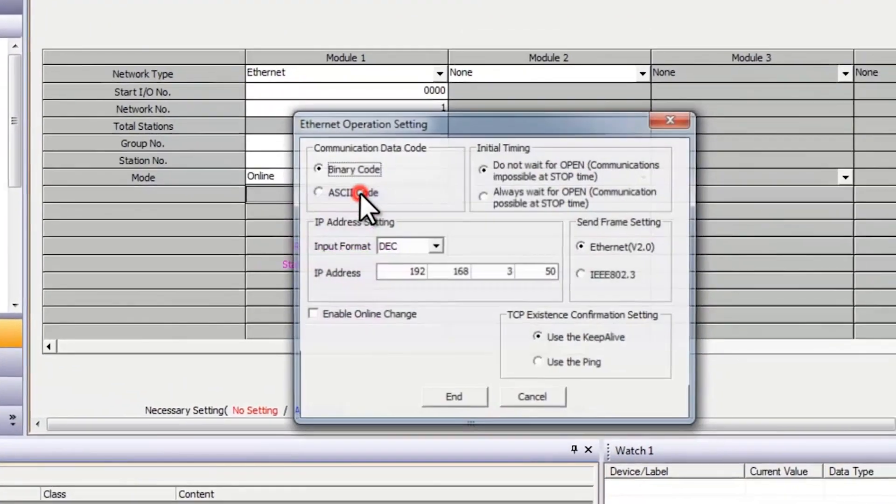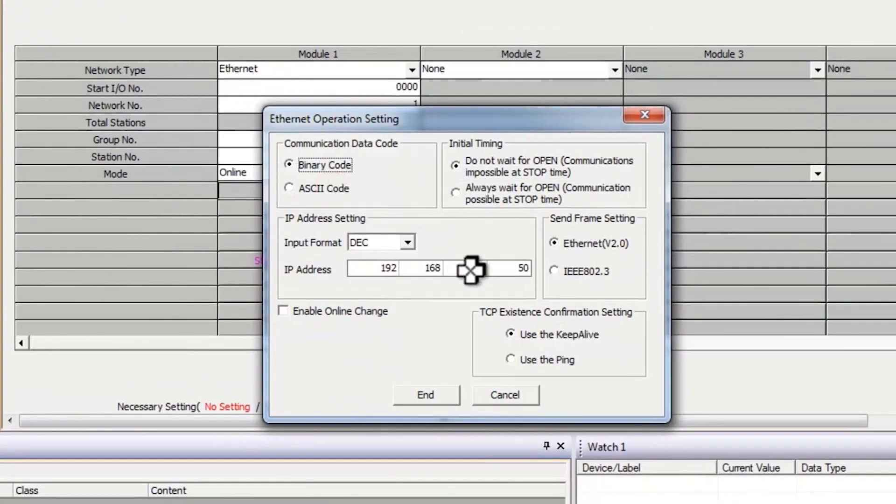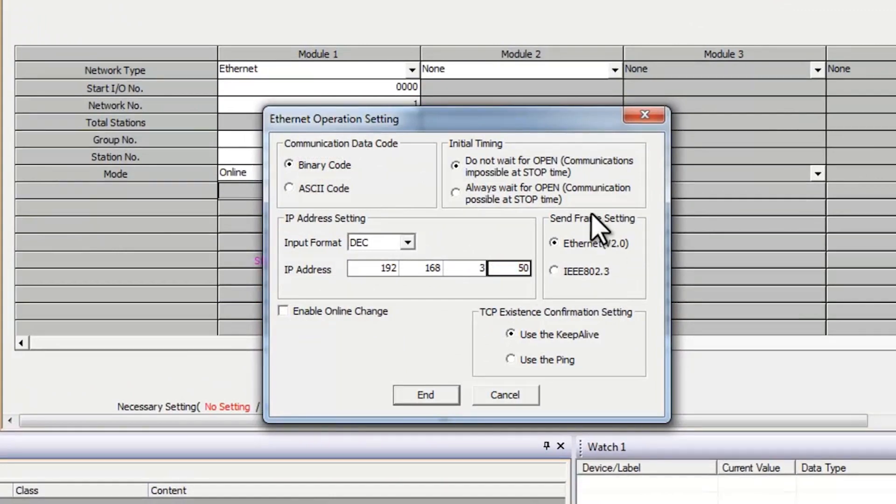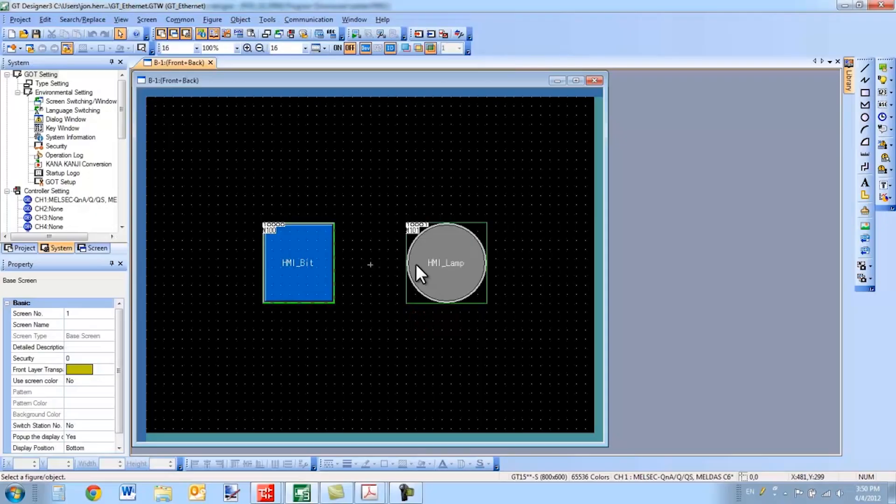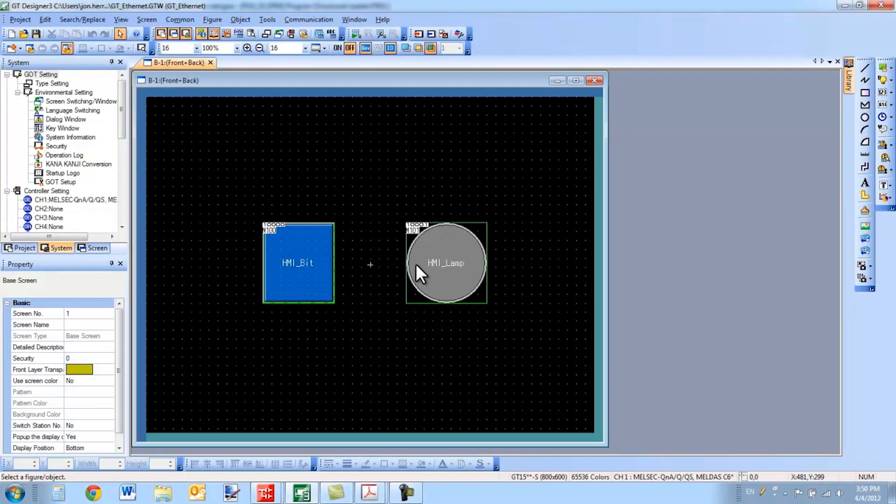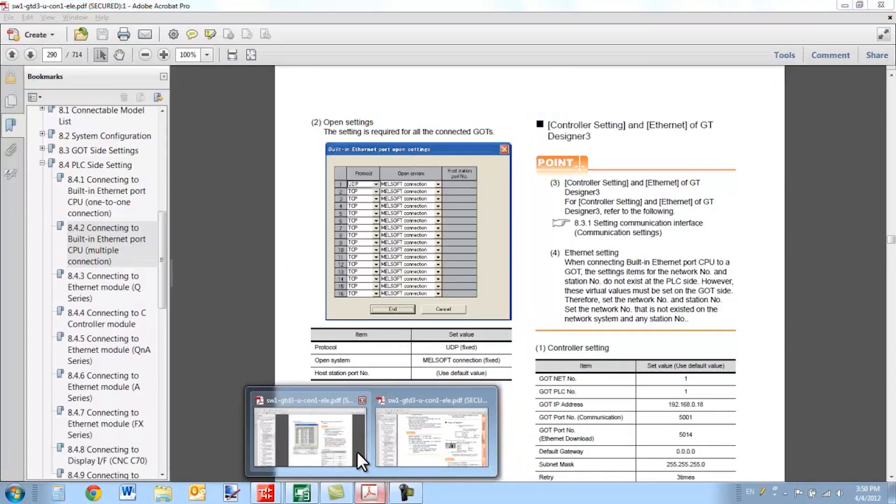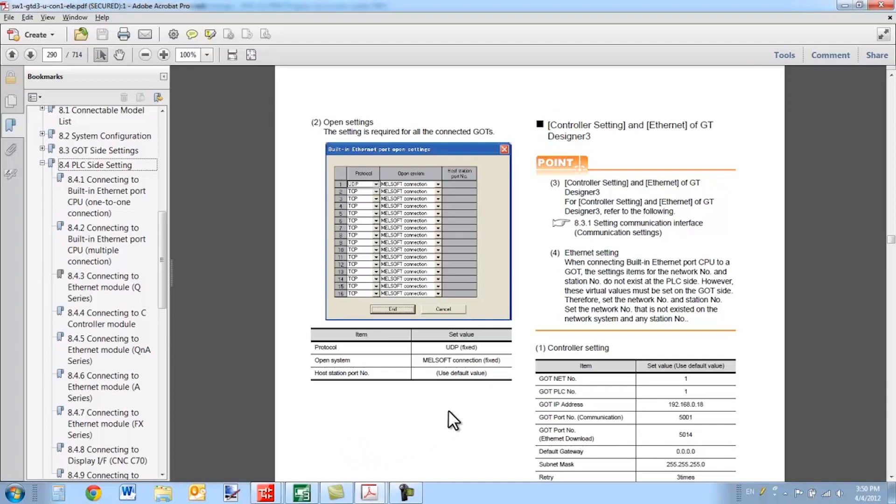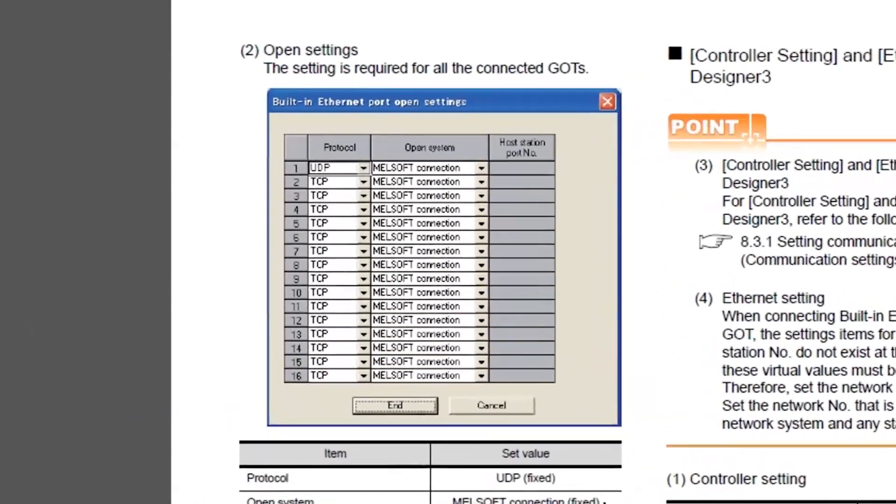And lastly, for the operation settings, configure your IP address. Everything else can remain the same. Other than that, everything should be straightforward. Make sure you refer to that manual for further information specifically related to an FX connection. If you're using a built-in Ethernet port on a Mitsubishi PLC, you need to have a UDP MELSOFT connection open for every GOT you have connected. It's recommended not to overload the built-in Ethernet port on the PLC. Thanks a lot for listening. Have a great day.